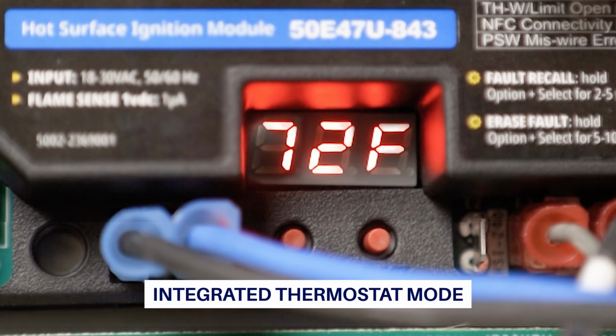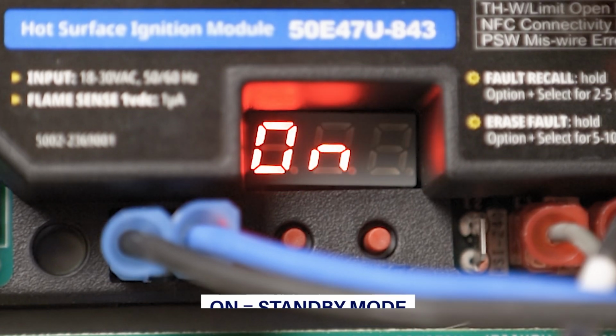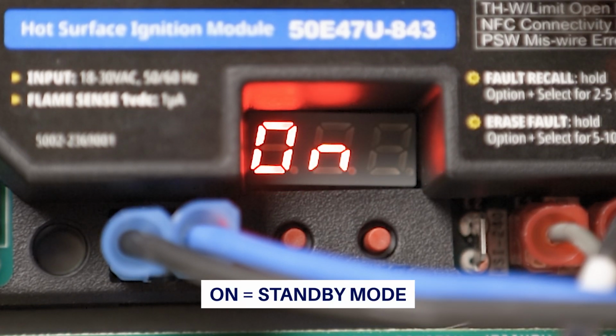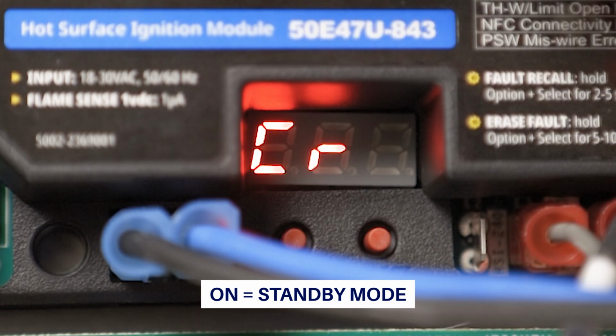The 50E47U-843 is compatible with applications using a built-in thermostat by using an onboard display. For these applications, the first 2 LEDs will show the sensor temperature and the third LED will display the configured unit of measure, either Fahrenheit or Celsius. If configuration was not completed using the White-Rodgers Connect mobile app, it can now be set up using the Option and Select buttons in the LED display. To enter configuration, press the Option button while the unit is in standby. For applications that have power only to THW, there is no standby mode.